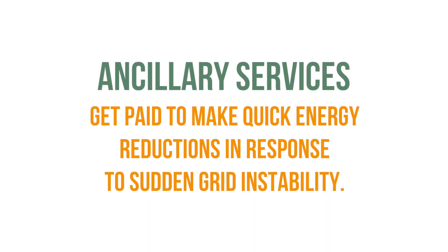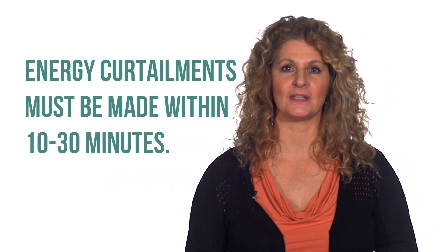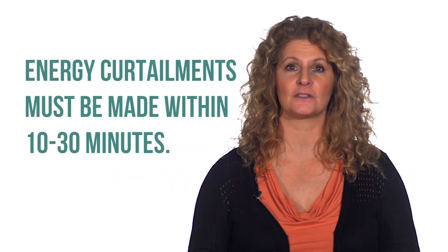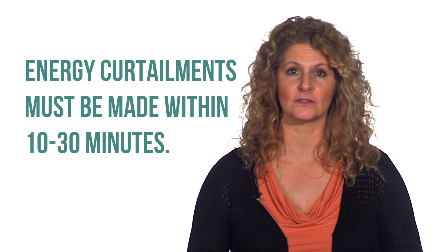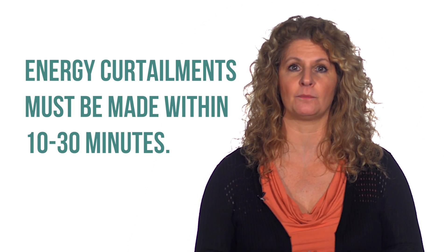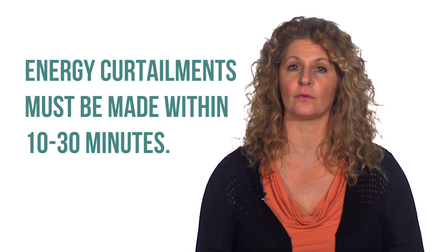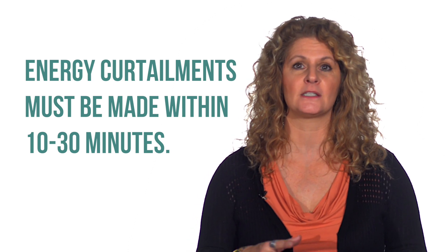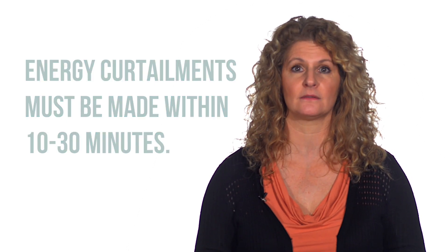Ancillary service demand response programs pay organizations to be on call to make quick energy reductions in response to sudden, short-term grid instability. They are similar to capacity programs with the exception that participating organizations must curtail within short notice of being called on by the grid operator, typically within 10 to 30 minutes.